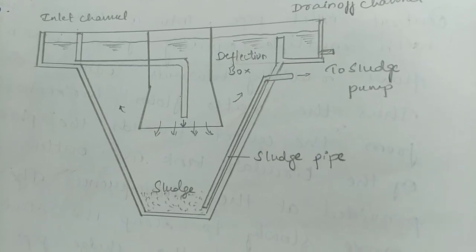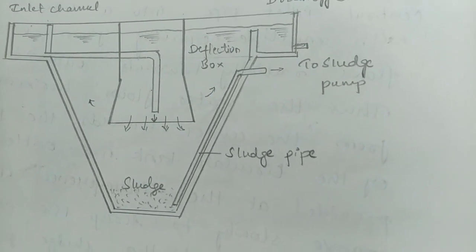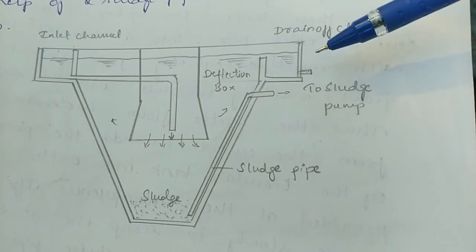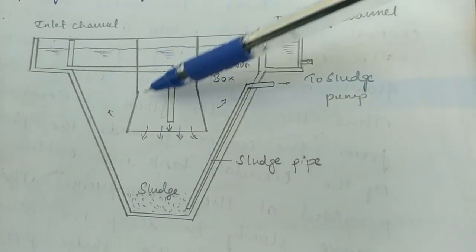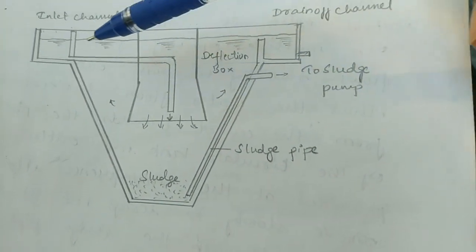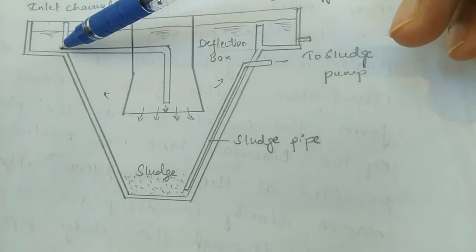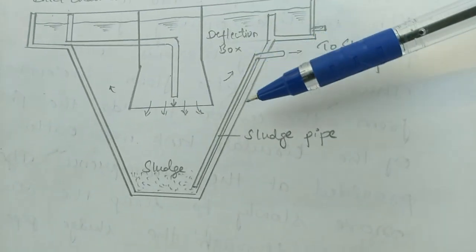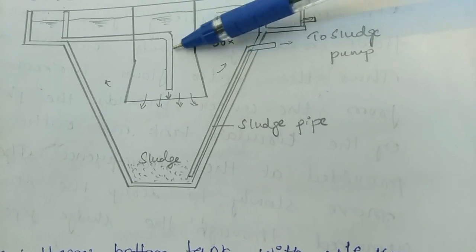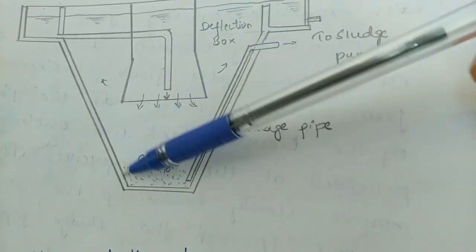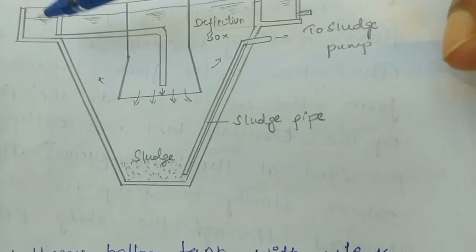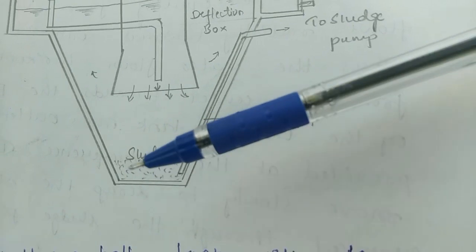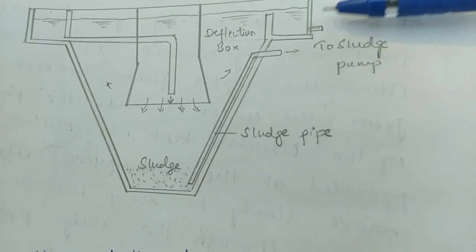The third type is the hopper bottom tank with vertical flow. Its components include an inlet channel, a drain-off or outlet channel, and a deflection box. Raw water enters from the inlet channel and is distributed evenly by the deflection box. The water is given rest, and the particles that settle at the bottom as sludge are taken out from the sludge pipe and pumped off.